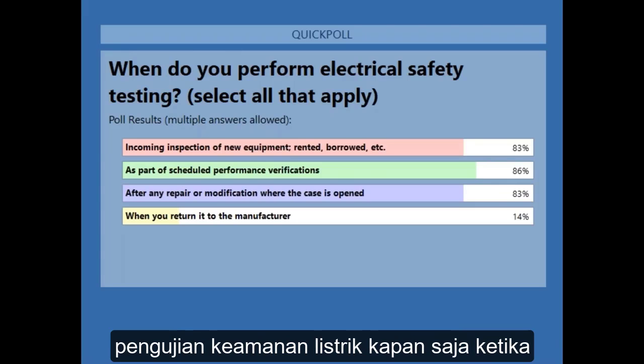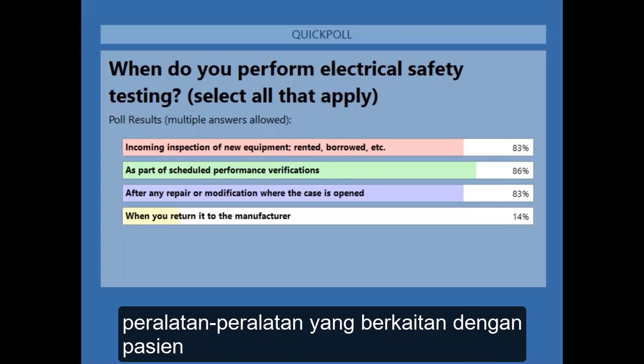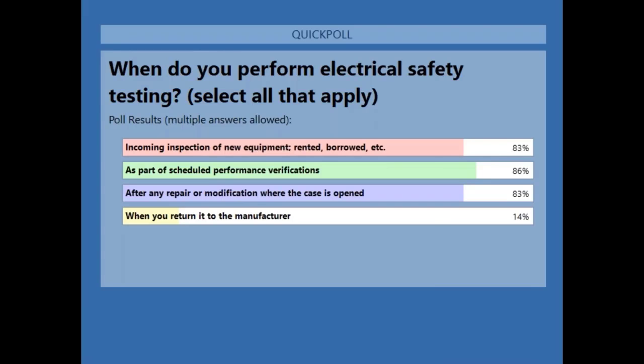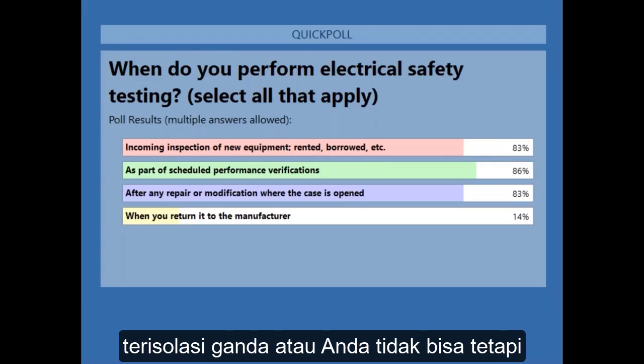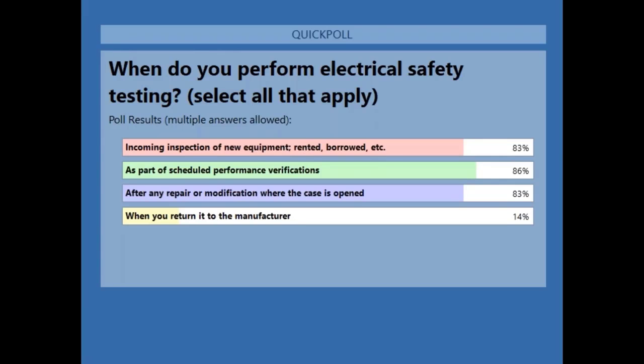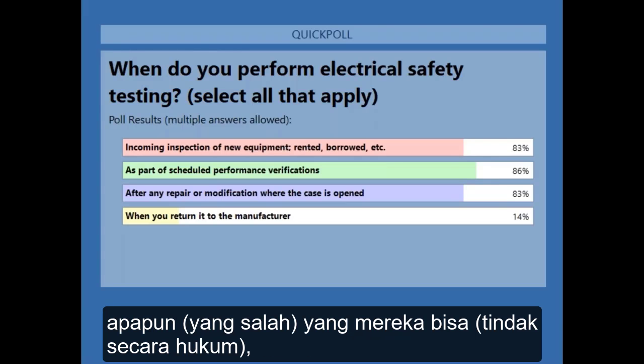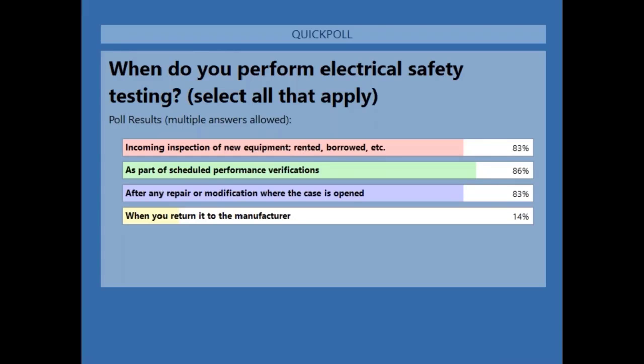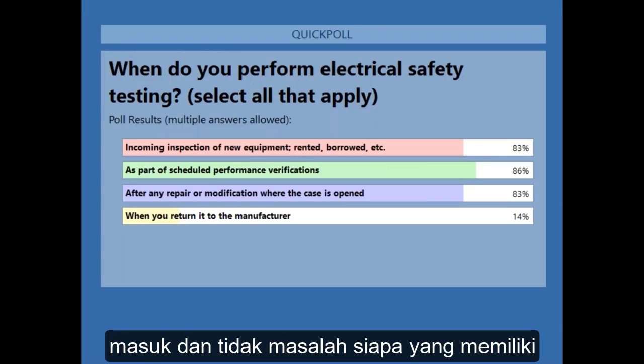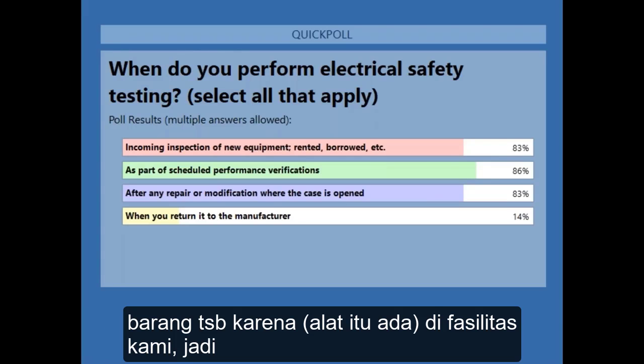NFPA 99 actually makes it fairly clear that you are to perform electrical safety testing anytime a piece of patient-related equipment comes into your facility. Now, there are some examples where it may be double insulated, where you can't, but anything that comes into your facility, you need to remember you are responsible for that. In this litigious society we have now, we know how people will try to find anything they can. So if we are doing our incoming inspections, if we're doing our safety testing on that, that takes one thing out of it, that yes, we can prove we did our due diligence when this came in, and it doesn't matter who owned it because it is in our facility. So it is literally ours to verify at that point.